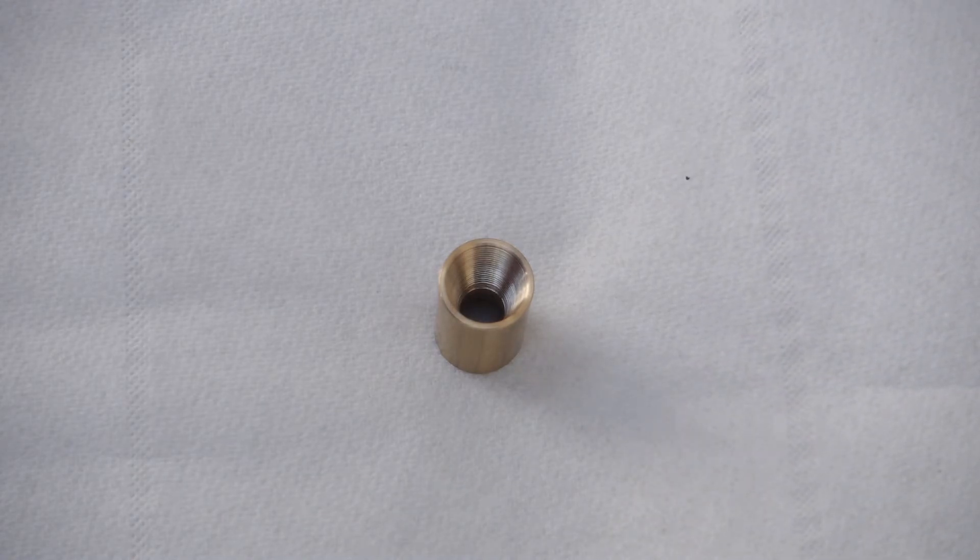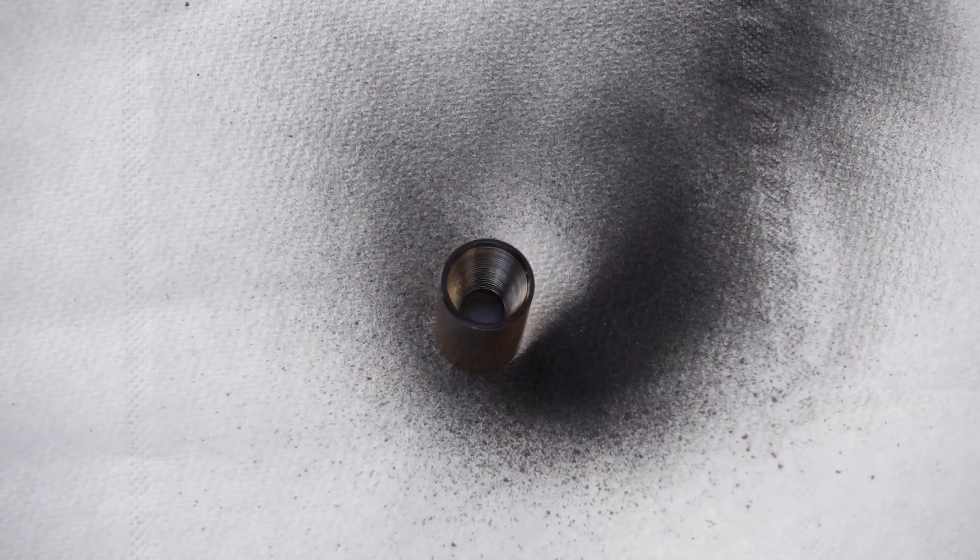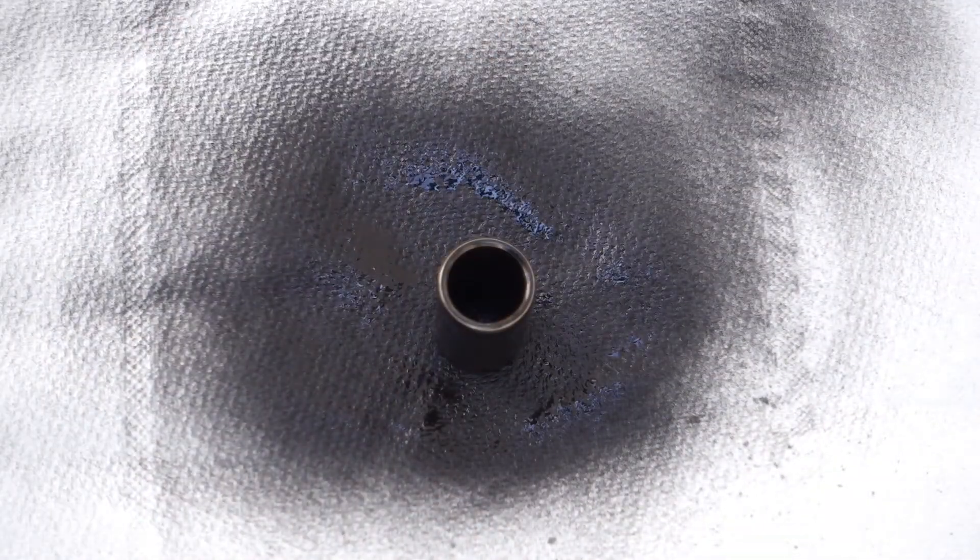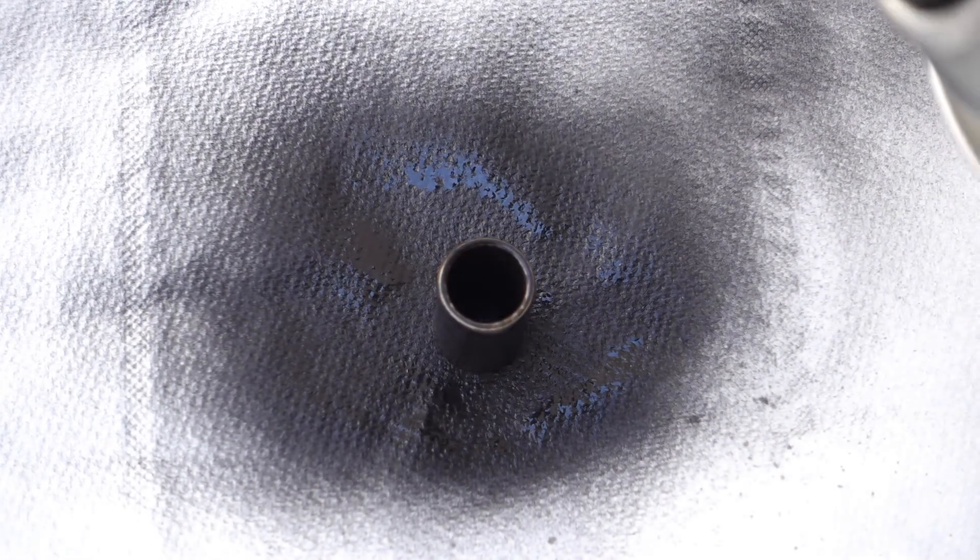It is important that the walls are absorbing infrared light and not reflecting it. High emissivity black paint or black anodized aluminum are a good choice for the surface finish.